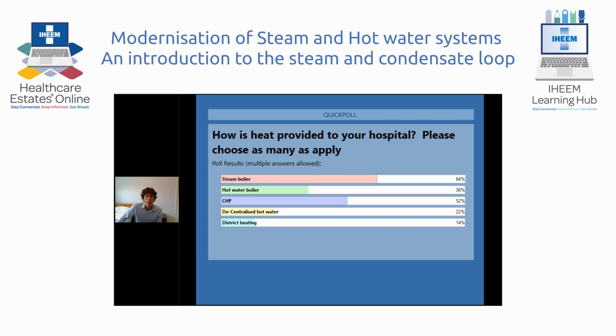I mentioned the scale formation. As we're continually condensing in the boiler, to maintain TDS, or total dissolved solids, that's the salts that we're concentrating in the boiler, we need to continuously blow down some of the water within the boiler to prevent those concentration levels from getting too high. This blowdown is another type of loss. The boiler itself is physically a large vessel and loses heat from its surface. These shell losses are around 4%, although for boilers that are operating on standby or low fire duty, as a percentage of the total consumption as a fixed amount, then this can increase considerably.